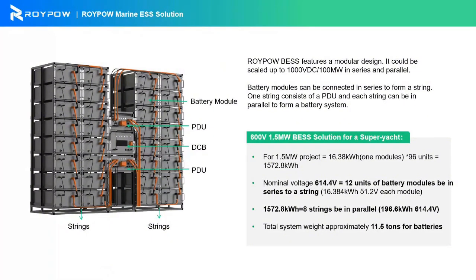It can be scaled up to 1000 VDC and 100 megawatts, in series and in parallel. The battery modules can be connected in series to form a string, as you can see, one string, and the strings can be paralleled to form a battery system. This is a whole battery system, and battery systems can also be paralleled into a large battery system, up to 100 megawatts.